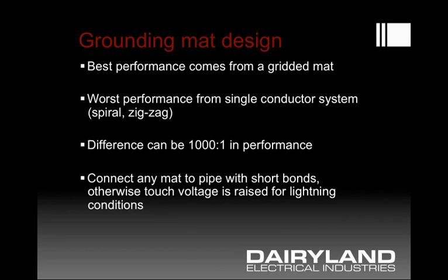The best performance in a grounding mat system comes from a mat with a grid style. Compared to a mat made up of a single wire — whether spiral, zigzag, or any other shape — a single-conductor system has a very long length. Long lengths have high inductance, and for a lightning event, high inductance produces very high voltages. The difference between these two mat designs could be as much as 1,000 to 1 — a very large performance difference, all because of inductance.